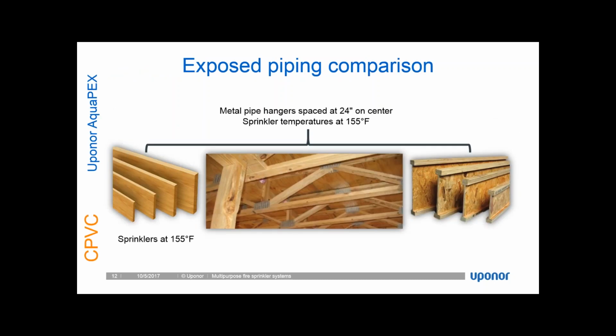So when I look at a CPVC application, I still need the sprinklers at 155 degrees or less, but I also have to use smaller spacing for those sprinklers. And this is why we had 9 sprinklers instead of 7 sprinklers, because I'm limited on how those sprinklers can be spaced in that basement application, depending on which way the joists are running. I also have directional limitations. So when we actually get into the layout of the systems, we're going to see that the mains have to run a certain way and the branch lines have to run a certain way in accordance with the listing.